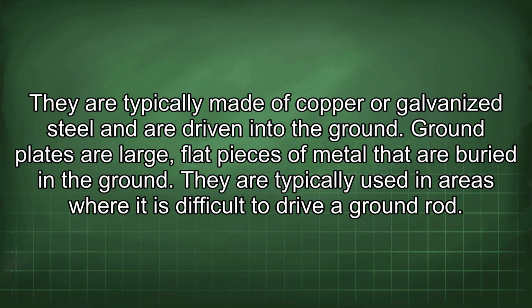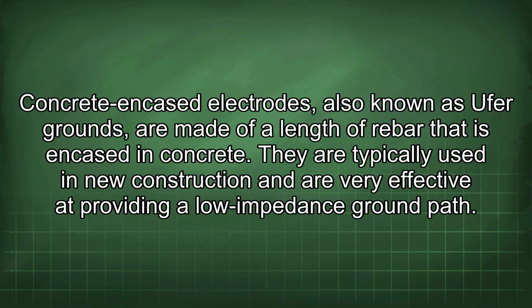They are typically made of copper or galvanized steel and are driven into the ground. Ground plates are large, flat pieces of metal that are buried in the ground. They are typically used in areas where it is difficult to drive a ground rod. Concrete encased electrodes, also known as Ufer grounds, are made of a length of rebar that is encased in concrete. They are typically used in new construction and are very effective at providing a low impedance ground path.